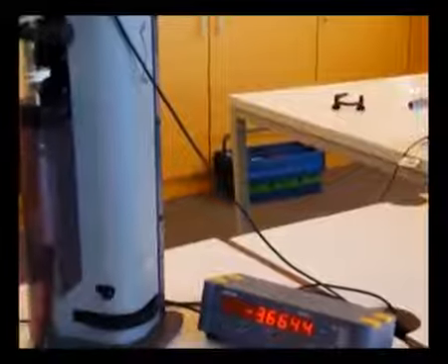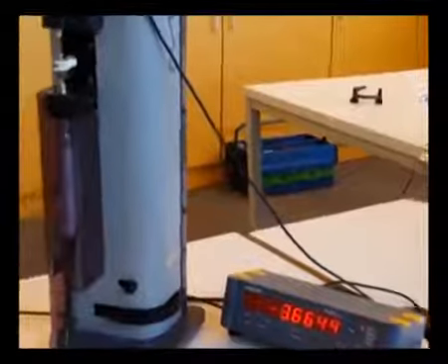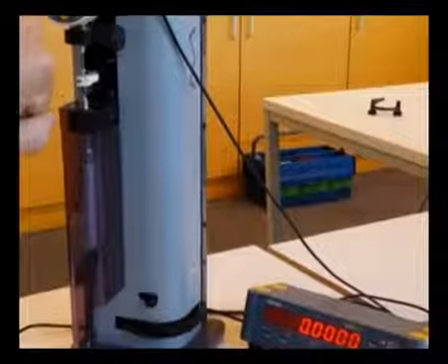Once I have touched the dial gauges, I can make a preset, and this will zero my gauge, but also the master unit. Then we can start the measurement, enter a serial number, and go up to the predefined points I have put.